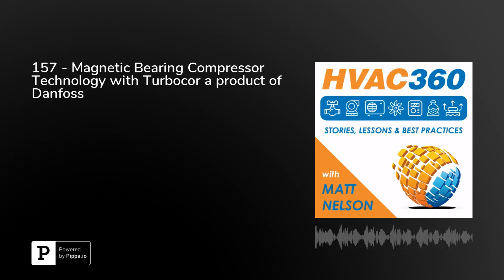How do the compressors handle that sort of situation? Yeah, with the compressor, we do need power in order to levitate the shaft. But what happens if you have a very brief loss of power, just a few milliseconds, or a voltage sag of a couple of seconds? The compressor can breeze through that, no problem. It just keeps going. But if it sees a voltage sag that lasts more than a few seconds or a total loss of power, it will go into a state that we call generator mode.